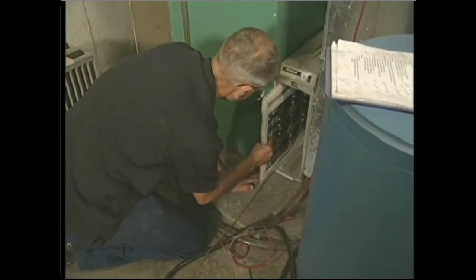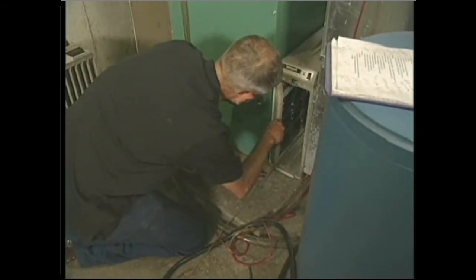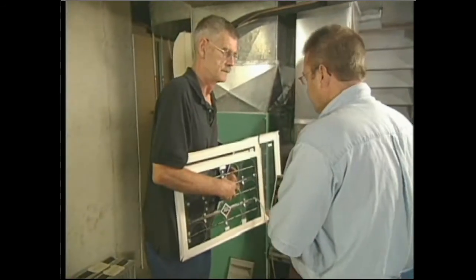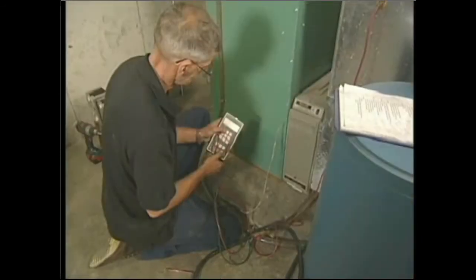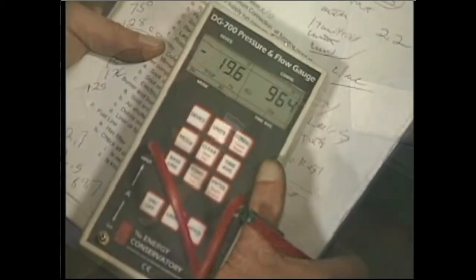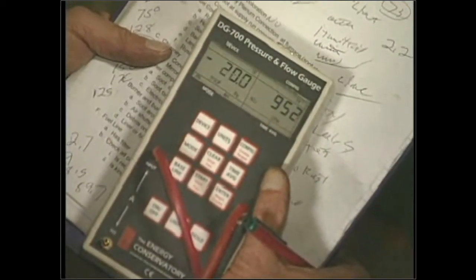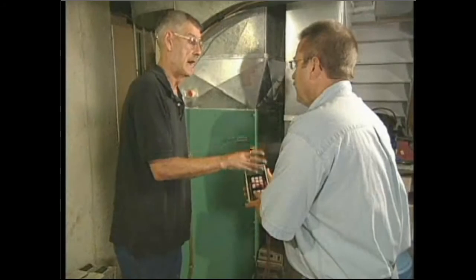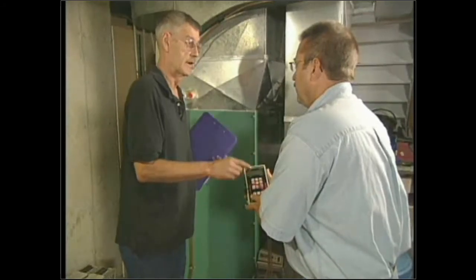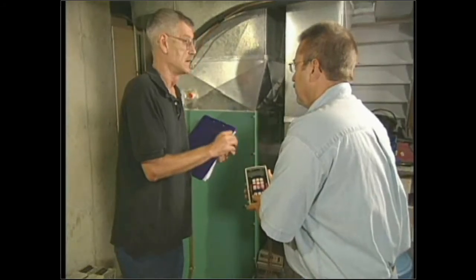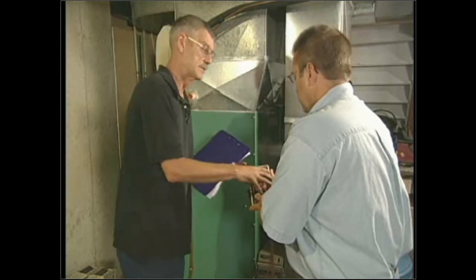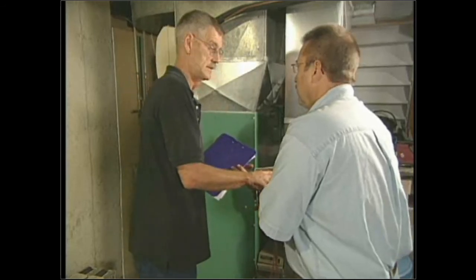When we put the flow plate in, we want to make sure these diamonds always face into the airflow. Okay. And then we select the plate, and then we read the reading. Now, some manometers are different. Some of the older manometers, you have to do a correction factor. You have to go to a chart and find a correction factor, because it doesn't have it built in. This model has it built in, so I don't need to do the correction factors.